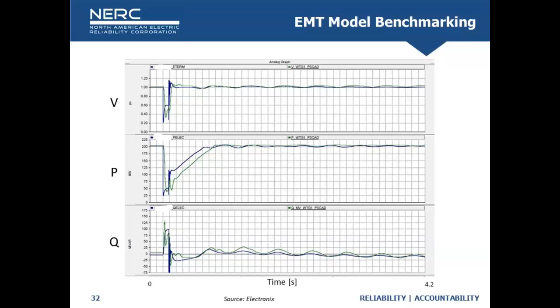A lot of utilities are starting to demand that the EMT model be benchmarked against the generic positive sequence model, to ensure the models reasonably match. That generic model isn't a set of default parameters; it's the actual equipment being used, because the EMT model is typically very detailed and very accurate.